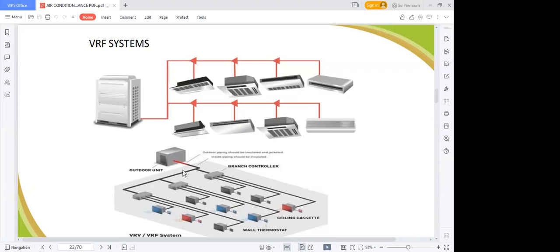Then the way you see they are powered here, you see a central system, then you see all the units directed. So they also have the capacity to produce heat in a particular area, and they can also produce cooling. Why do they call it variable refrigerant flow? What causes effective cooling within the system is the flow of your refrigerant. The other ones we have been talking about all have constant flow of refrigerant, so it cannot be fully regulated. With the VRF system, when you regulate this, it reduces the energy consumed by your compressor. I believe I'm making sense. Those of us that are engineers will understand more, but take note, your VRF saves more energy than your chiller system.